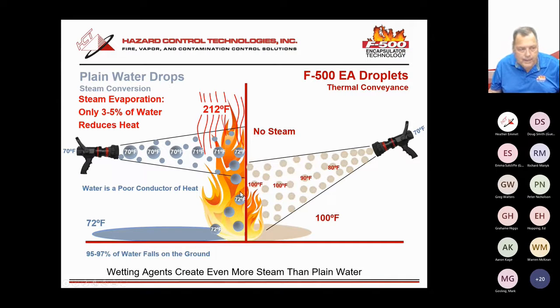So we're creating a heat sink. Here's your plain water coming out of the hose at 70 degrees F. The droplet, let's say 95 to 97% of it remains right at 72 degrees. The outer part, like an onion, converts to steam. You get marginal heat reduction, and you need to use copious amounts of water.